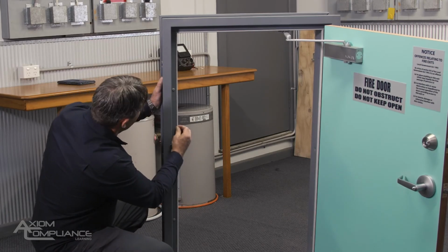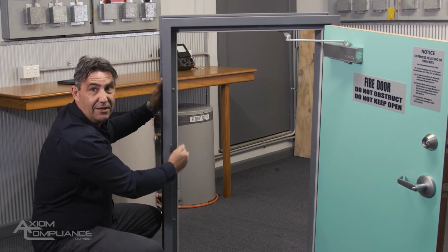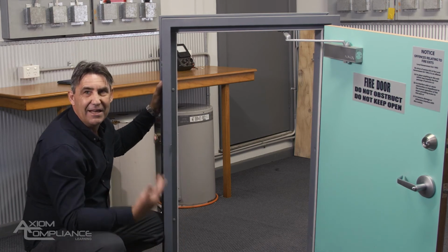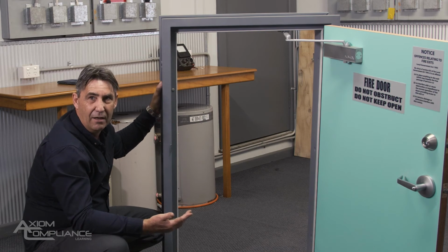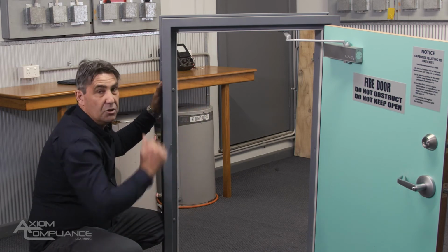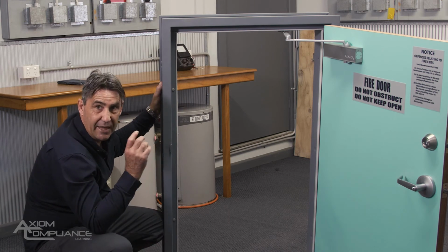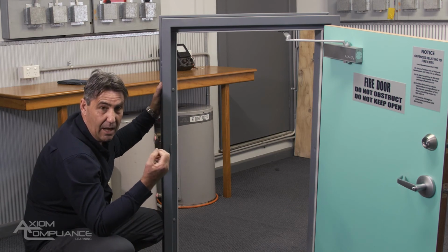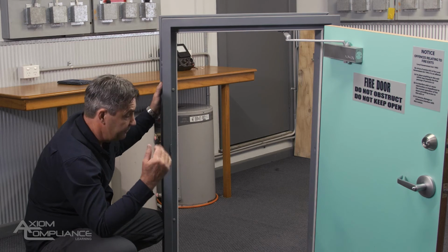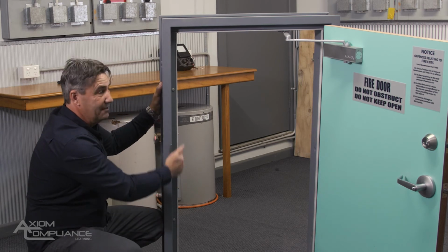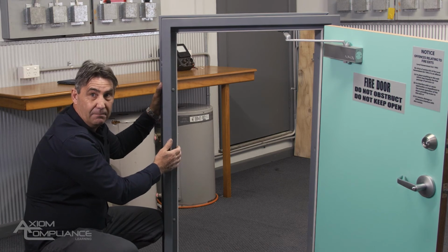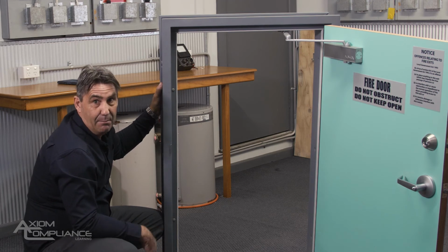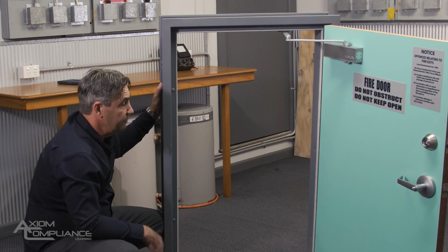Now when you inspect the seals, just try and push them up and down a little bit, because they do move inside their sleeve, and just make sure that they're all in good condition. And once again, is that seal rated for fire? This particular door has a 2-hour fire rating, and when we have a close-up look at that label, I'll show you the rating plate, and it tells you on the rating plate how many minutes the door is meant to last under fire conditions. So we have to make sure that any of these additional hardware items are fire rated. And once again, that'll go into our register, and we'll have that as our baseline data and not have to worry about it anymore, because we've already checked it out.